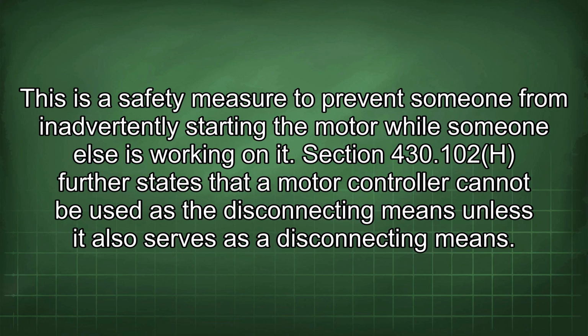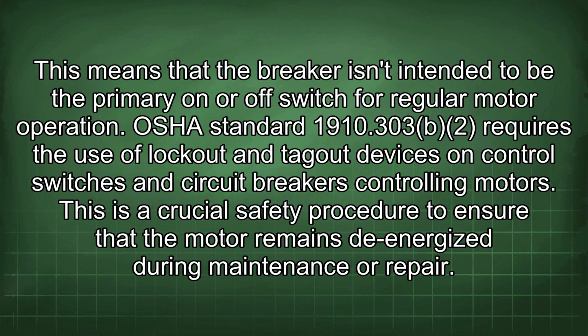Section 430.102H further states that a motor controller cannot be used as the disconnecting means unless it also serves as a disconnecting means. This means that the breaker isn't intended to be the primary on or off switch for regular motor operation. OSHA Standard 1910.303 requires the use of lockout and tagout devices on control switches and circuit breakers controlling motors. This is a crucial safety procedure to ensure that the motor remains de-energized during maintenance or repair.